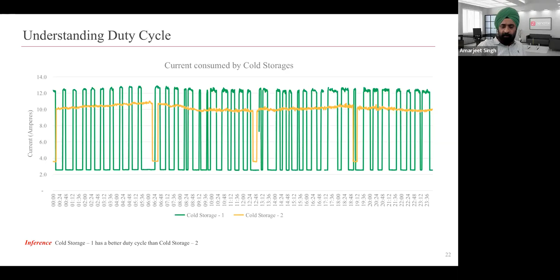Very high duty cycling is also bad, because that can make the compressor go bad since you are unnecessarily switching on and off. So your duty cycling should be in an optimal range, and our algorithms calculate this optimal duty cycling, and then we show that. So these are again some equipment, cold storages CS1 to CS8. For each of these cold storages, we have an ideal duty cycling range, and then there is a high and a low duty cycling range.